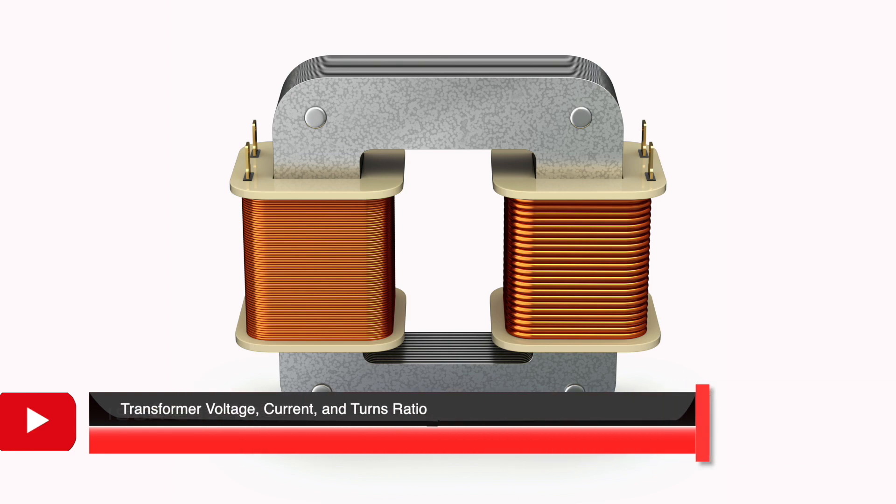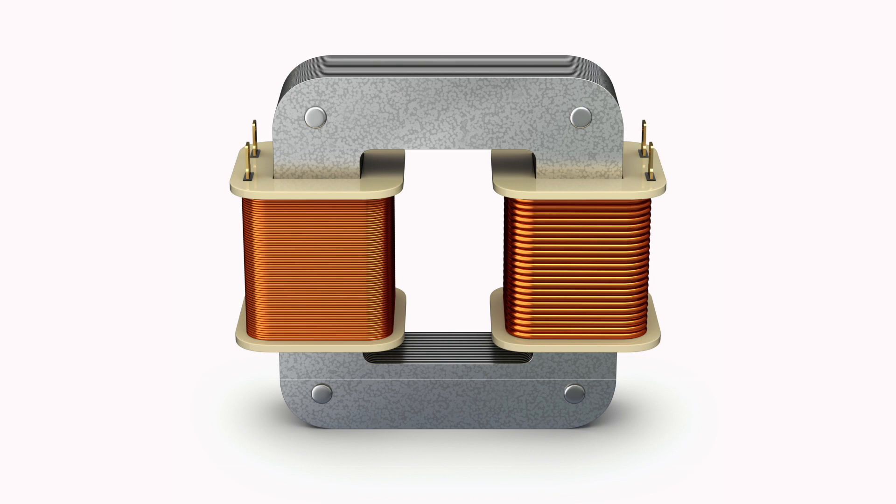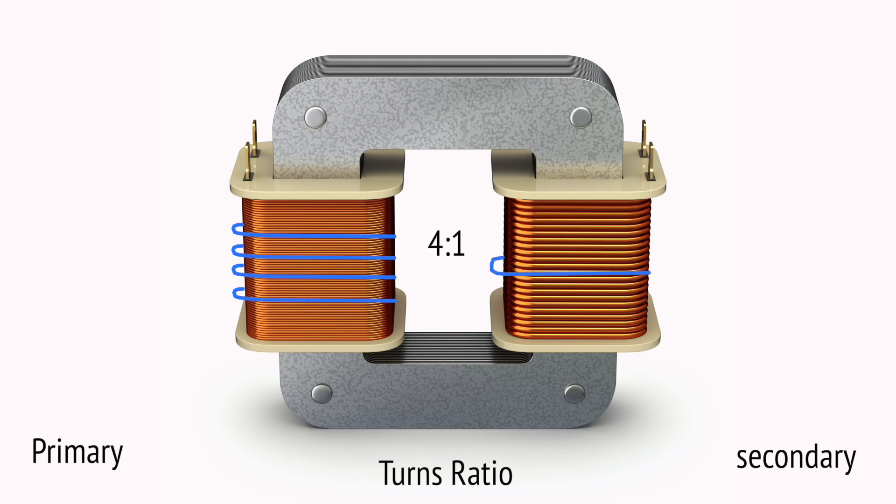What is the turns ratio in a transformer? The ratio of turns in the primary winding to those in the secondary winding is what's known as the turns ratio. For example, if a transformer has a 4 to 1 turns ratio, then for every 4 turns on the primary winding, there will be 1 turn in the secondary winding. Inputting 480 volts AC into the primary winding will produce 120 volts AC output on the secondary winding.